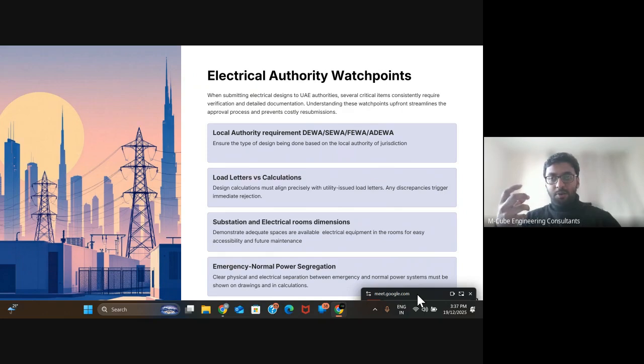Ensure you know the authority of jurisdiction for which the submission will be done. Generally this confusion happens in projects related to Sharjah and Northern Emirates. So before starting the design, ensure which particular or specific authority the submission will be for. Another important thing to look for is load letters and calculations. As I previously mentioned, ensure the load schedules match your local jurisdiction authority requirements. Number two, ensure the loads are properly indicated on the single line diagram.